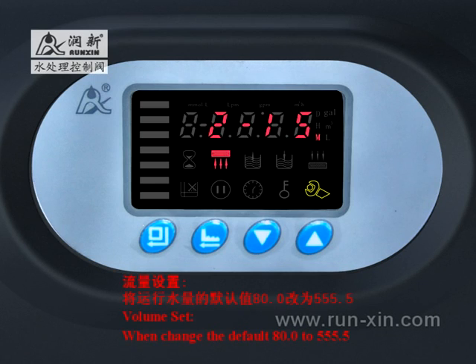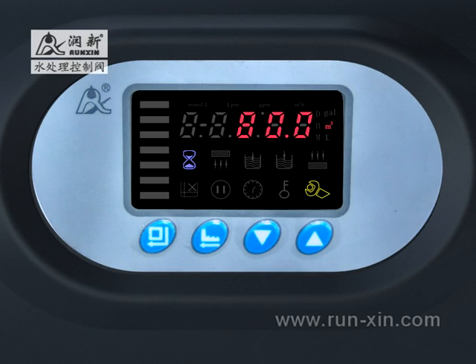Flow capacity setting. Change the default flow capacity 80 to 555.5. If the regeneration type is set as A03 or A04, it does not have the setting item of flow capacity. When the program is under inquiry state, press the up or down button until it goes into service state. Then press the menu button to get into flow capacity setting. At the same time, the setting symbol starts flashing.